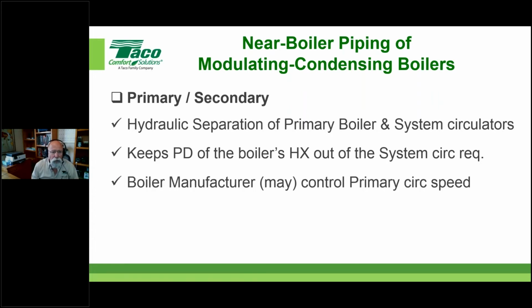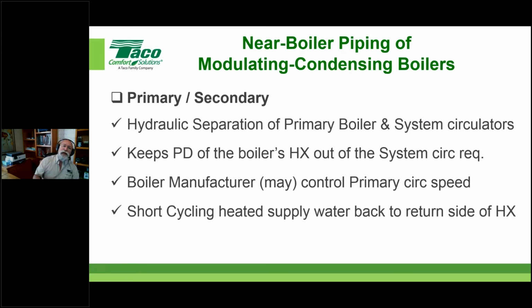Okay. So anyway, the boiler manufacturer nowadays can and may control the primary circulators, that's the boiler circulator, that can control its speed. We'll talk about that a little bit as well. And if we can do that, we want to do that and take advantage of that as well. One of the downsides of primary secondary piping is you have the possibility of short cycling water from the supply pipe that goes into the closely spaced T's backwards, I should say, and back up and into the boiler. And this will happen on some occasions. What we're trying to do with this little session is make sure you keep that to a minimum.